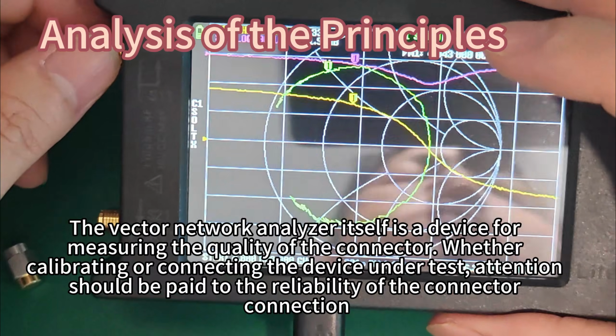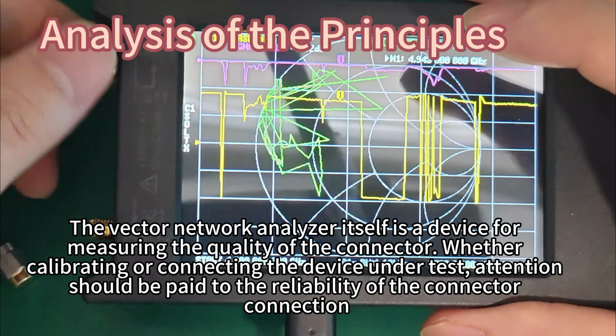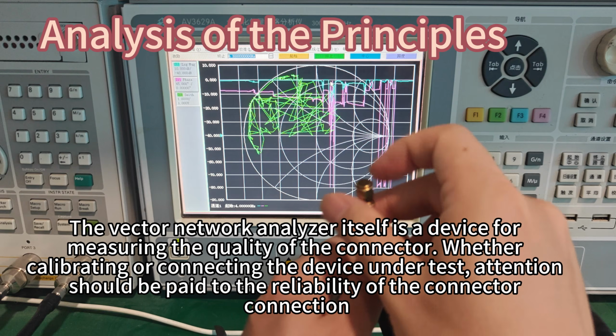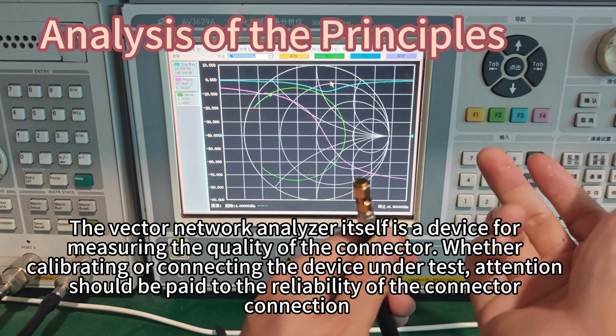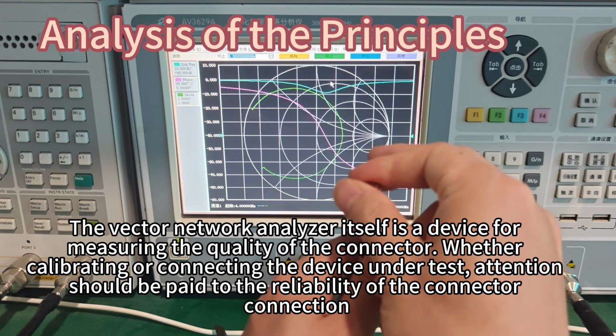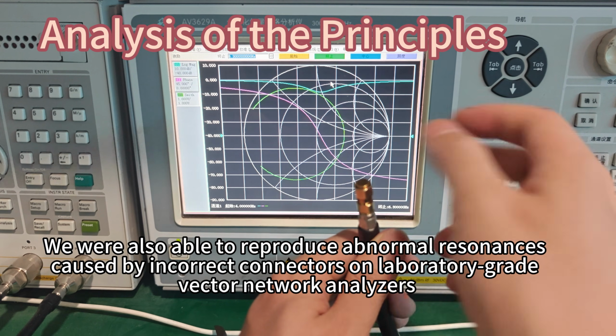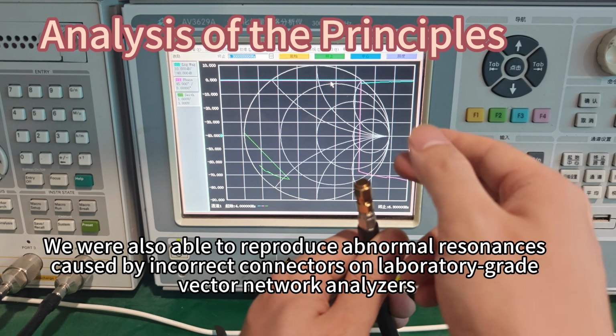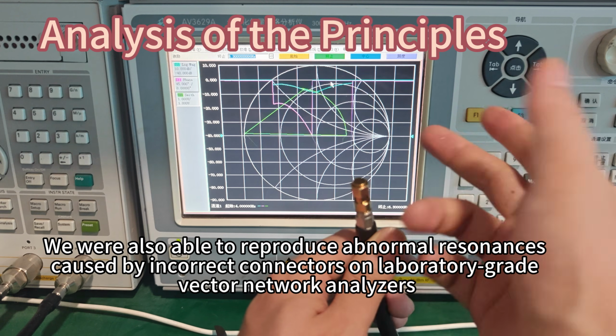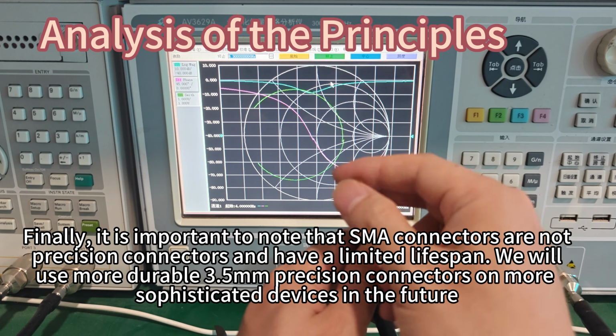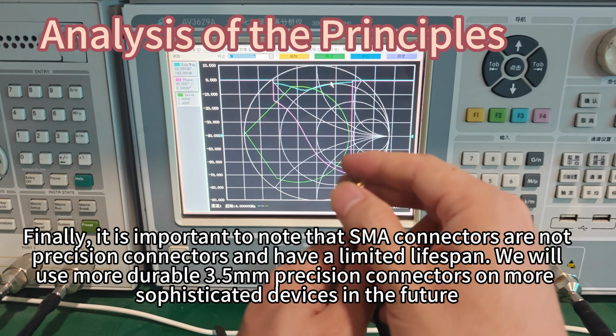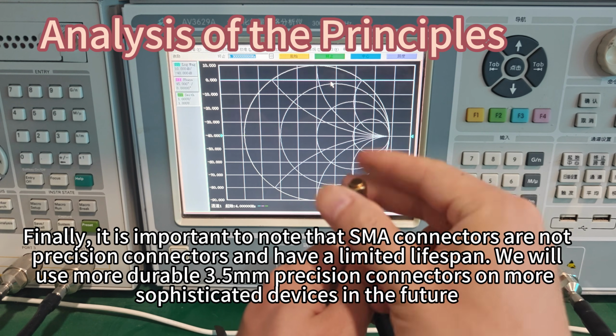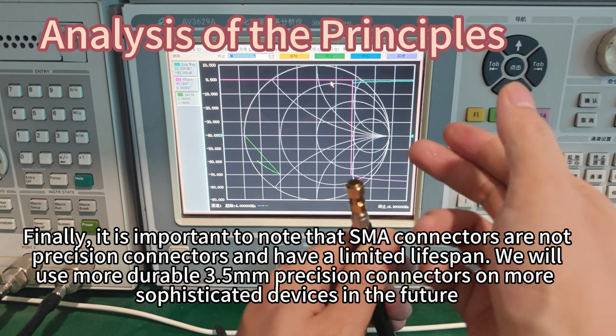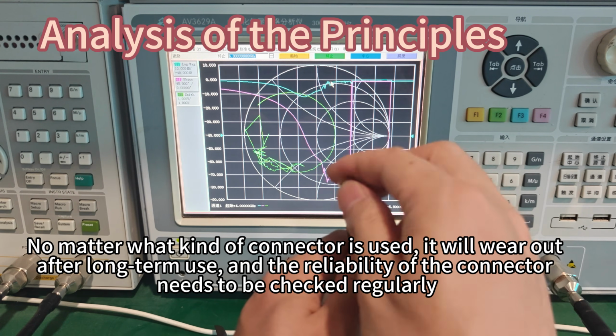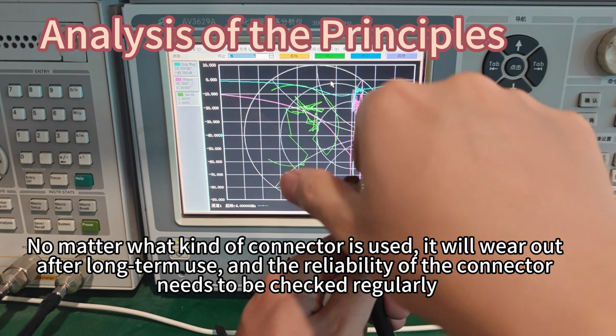The vector network analyzer itself is a device for measuring the quality of the connector. Whether calibrating or connecting the device under test, attention should be paid to the reliability of the connector connection. We were also able to reproduce abnormal resonances caused by incorrect connectors on laboratory-grade vector network analyzers. Finally, it is important to note that SMA connectors are not precision connectors and have a limited lifespan. We will use more durable 3.5mm precision connectors on more sophisticated devices in the future. No matter what kind of connector is used, it will wear out after long-term use, and the reliability of the connector needs to be checked regularly.